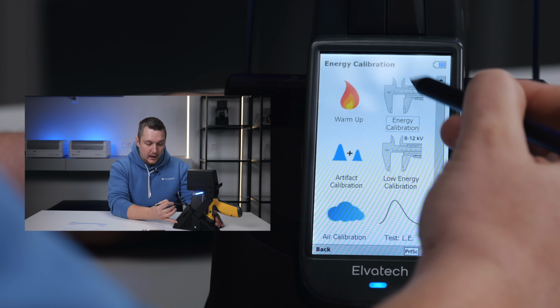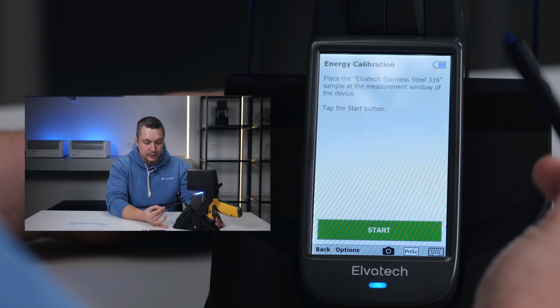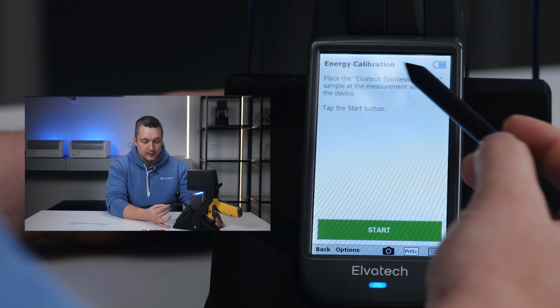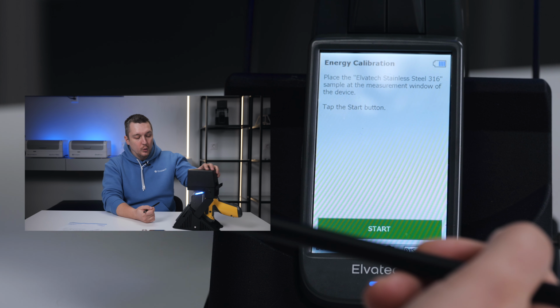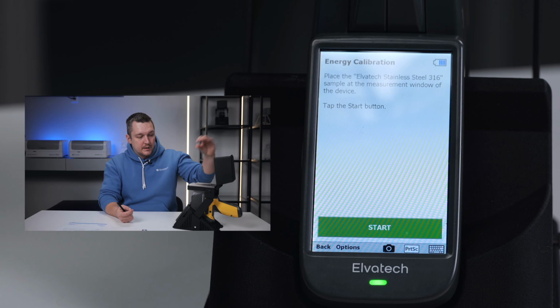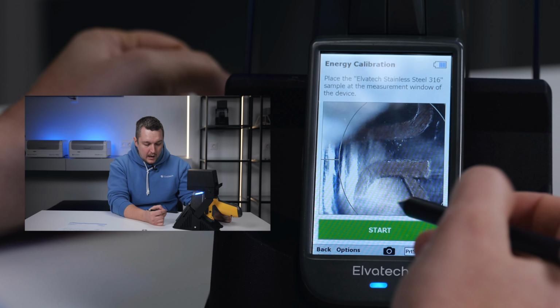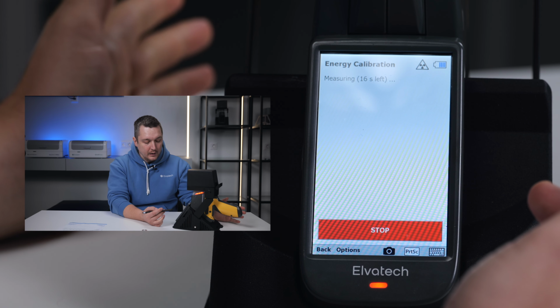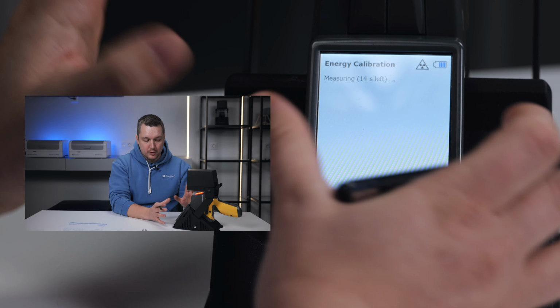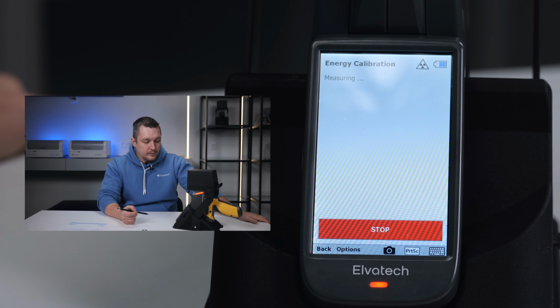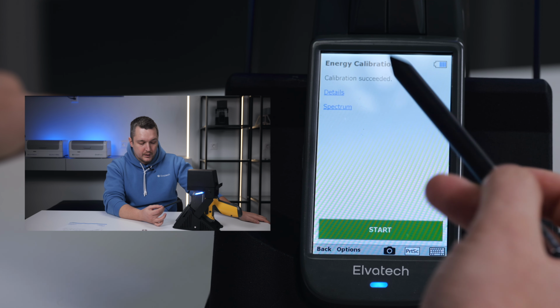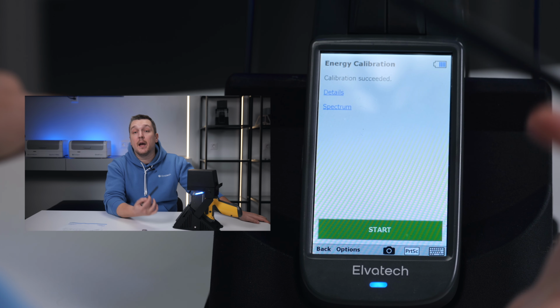And now we will click on the energy calibration. And you see on the screen there is a notice: place the Elvatech stainless steel 316 sample at the measurement window of the device and tap the start button. So we will do this. We will place the 316 sample and just press the start button. The procedure takes about 20 seconds, and you can change the time. It's the factory value. And we're just waiting for the results. And you see on the screen that calibration succeeded, and we have the details and spectrum.